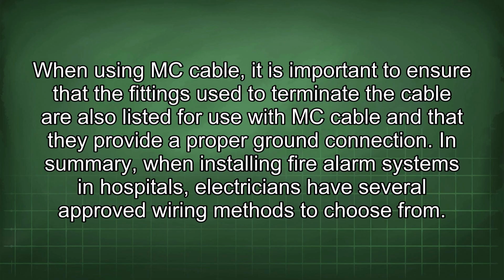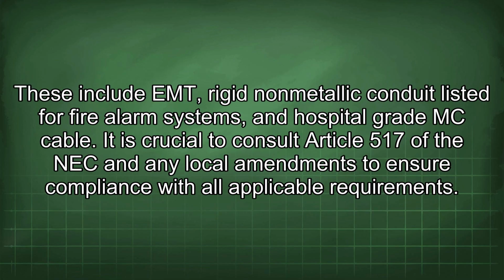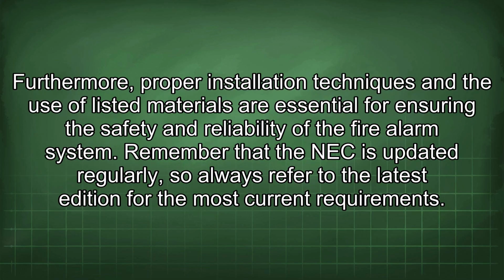In summary, when installing fire alarm systems in hospitals, electricians have several approved wiring methods to choose from. These include EMT, rigid non-metallic conduit listed for fire alarm systems, and hospital-grade MC cable. It is crucial to consult Article 517 of the NEC and any local amendments to ensure compliance with all applicable requirements. Furthermore, proper installation techniques and the use of listed materials are essential for ensuring the safety and reliability of the fire alarm system.